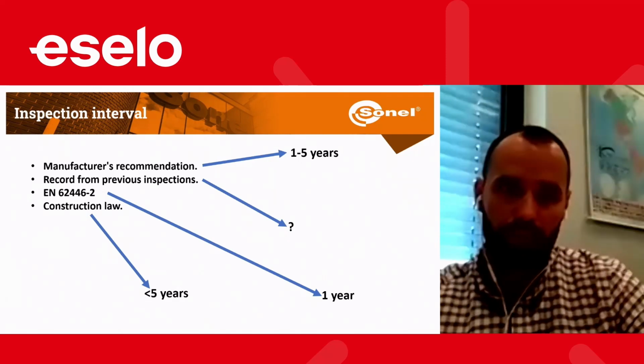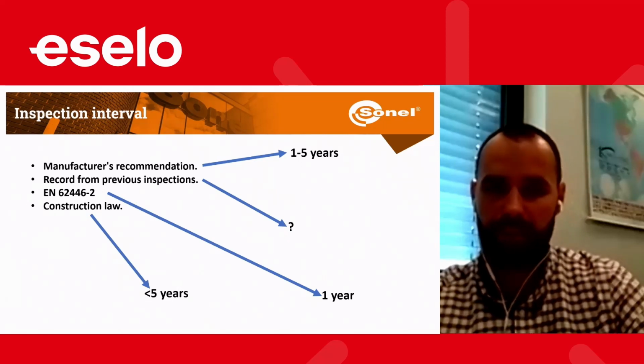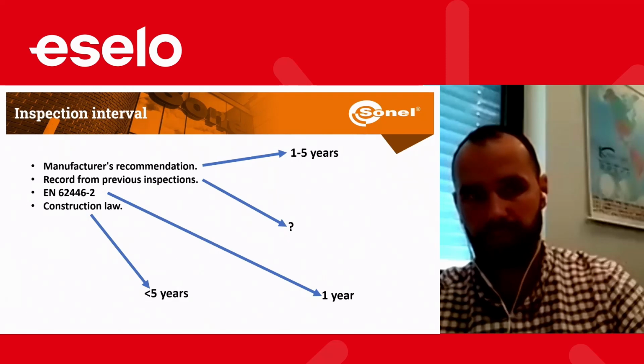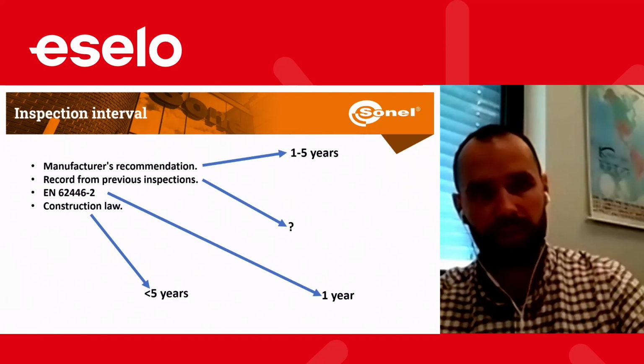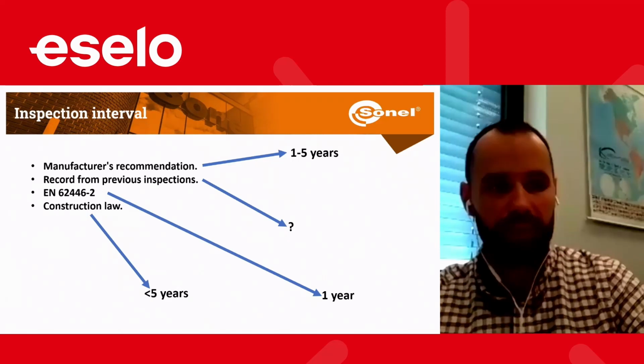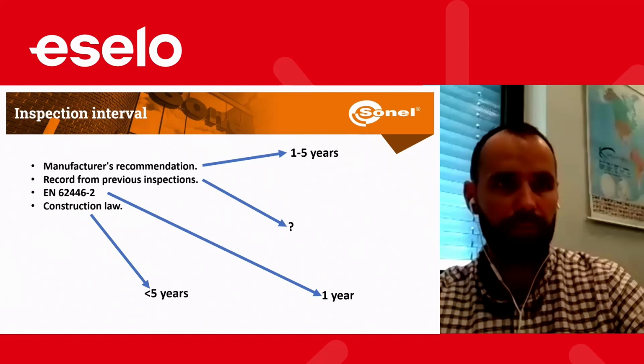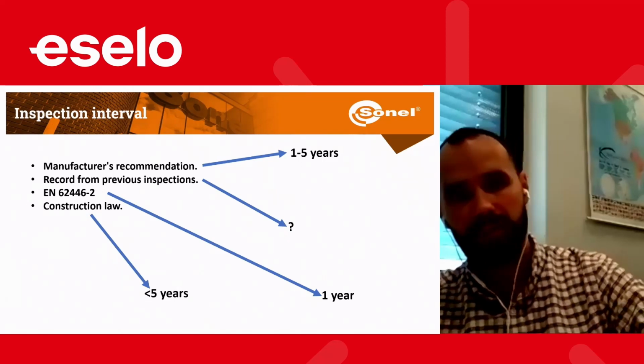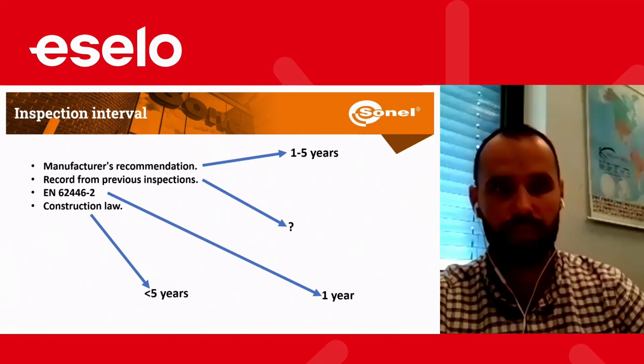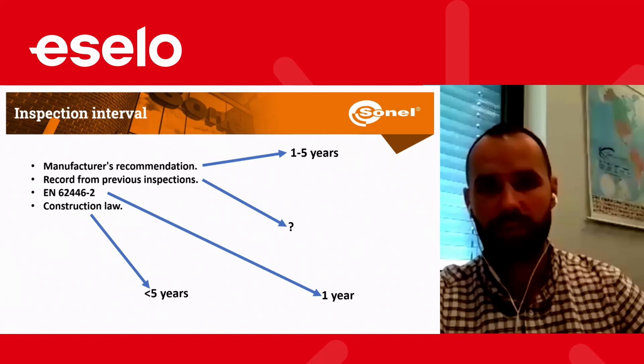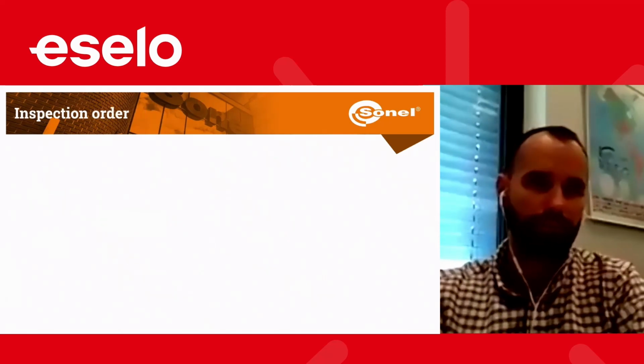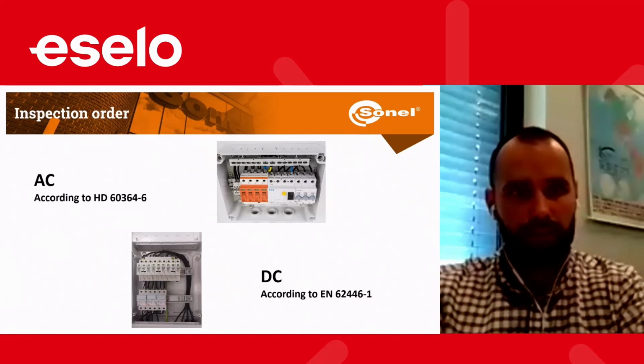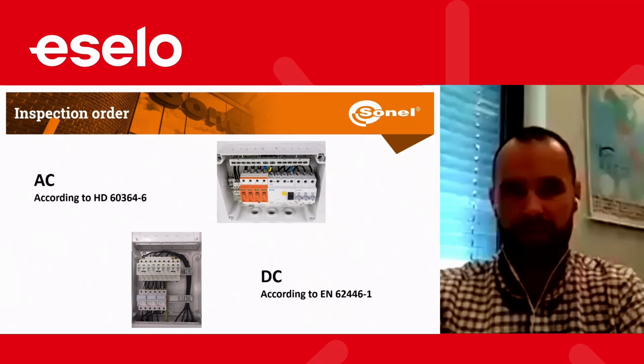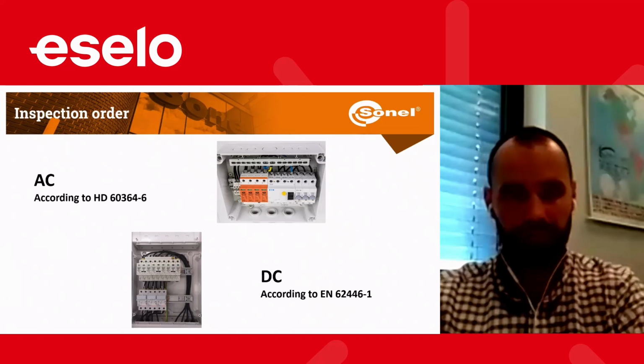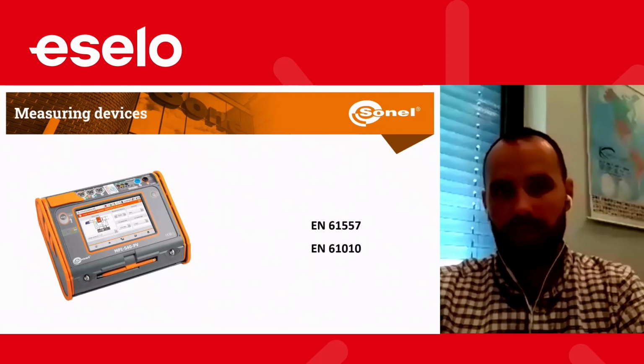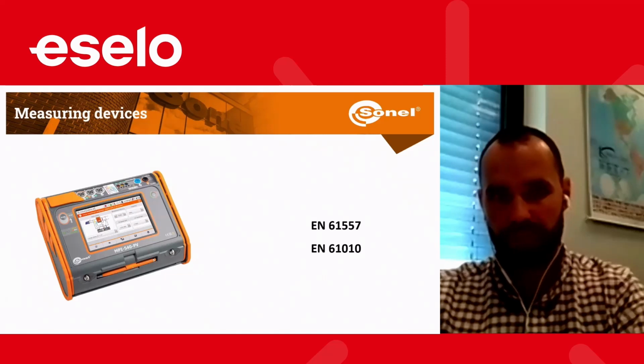The regulation of the norm, however, 62446, suggests to make the measurements every year. And in some countries, construction law is obligatory for everyone, because norms are voluntary. European norms are voluntary. However, if the construction law in each country is referred to some norm, it is obligatory to follow the norm as well. According to the standard, we should make the measurements on AC side and DC side. With our measurement unit MPI 540, we can make both sides of the measurement.